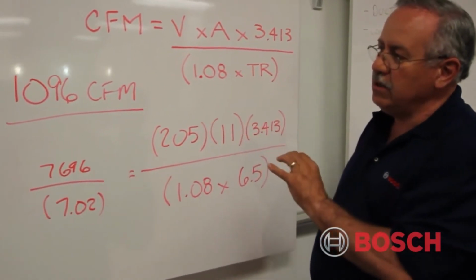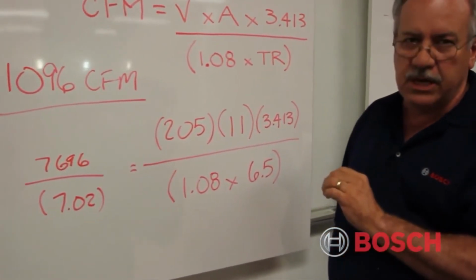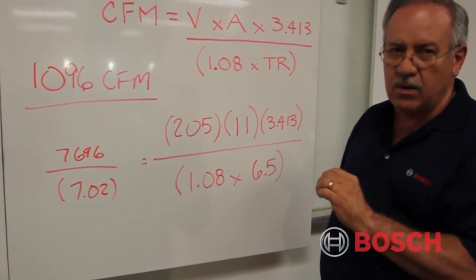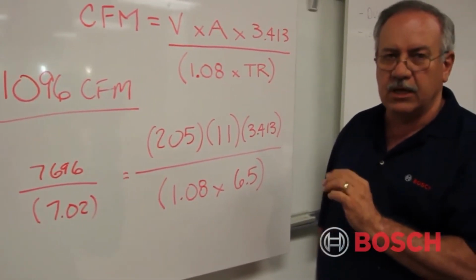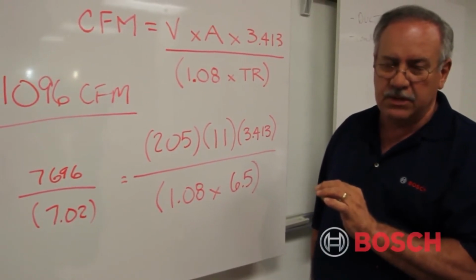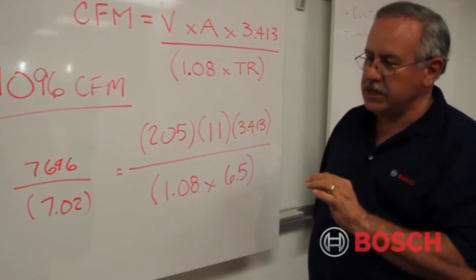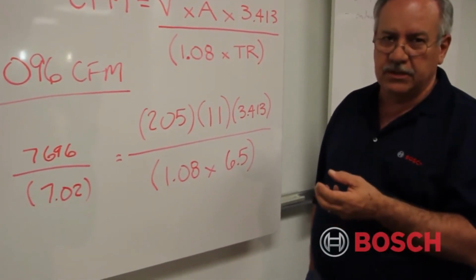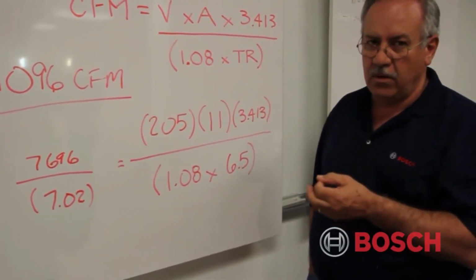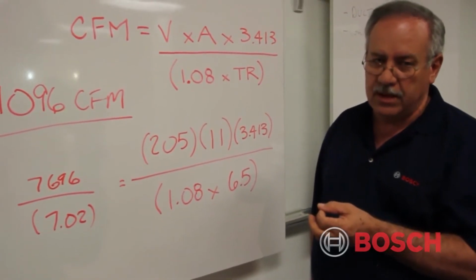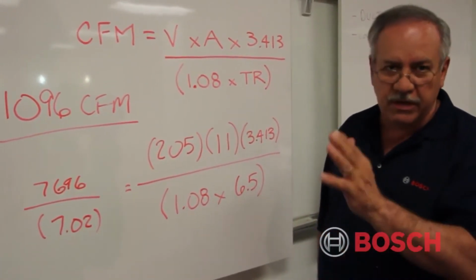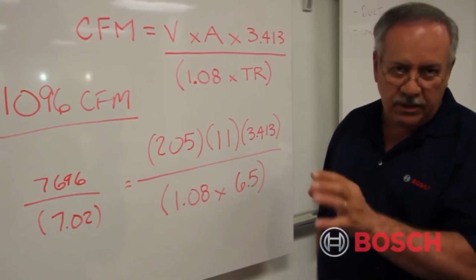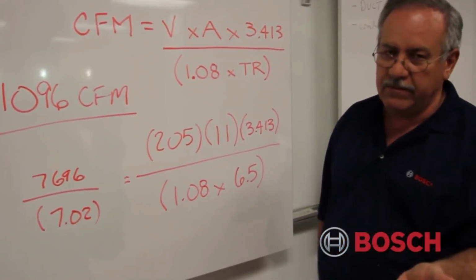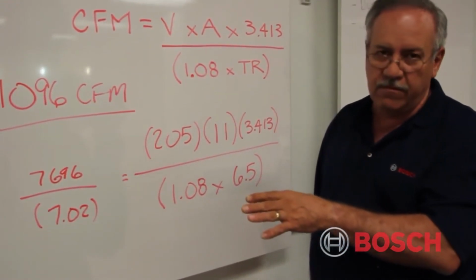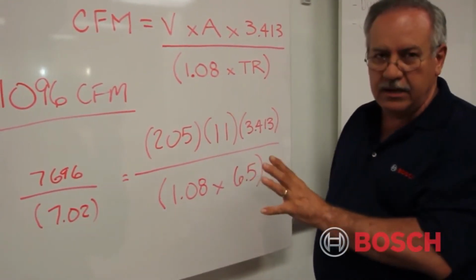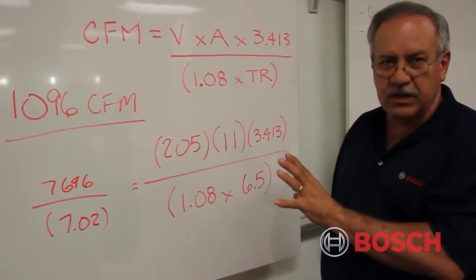Now what I'm trying to do ultimately is to determine CFM per ton that would be crossing the air coil of the geothermal heat pump in the cooling cycle. CFM per ton. The Air Conditioning, Heating, and Refrigeration Institute, whose tenets we follow, prescribes between 350 and 450 CFM per ton of cooling. So a lot of people say 400 CFM per ton is normal. So we're probably a little bit higher than that, but we can never be lower than 350 and theoretically not more than 450.